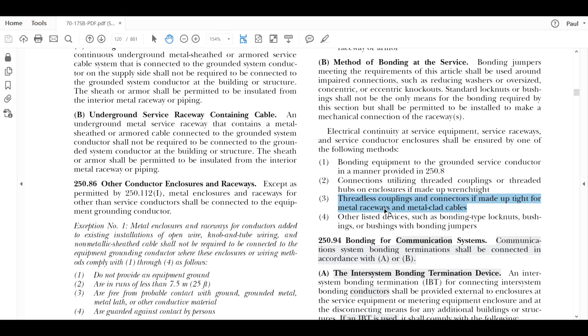We could do that. And then we have one other one that says you could use listed devices such as bonding type lock nuts. That's probably the most common. We'll use a bonding lock nut. Or I can use a bushing, which would be a bonding bushing. Or I could use a bushing with bonding jumpers. Okay, so I have all these options. Now, typically, I see the bonding bushing with the bonding jumper.